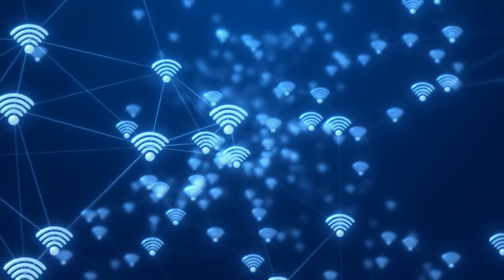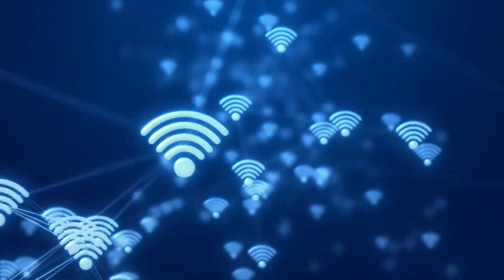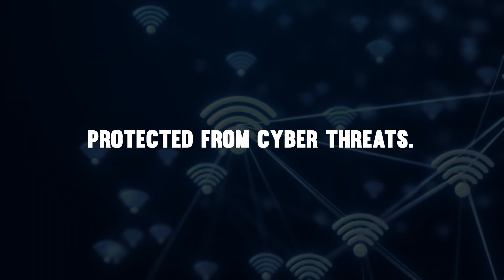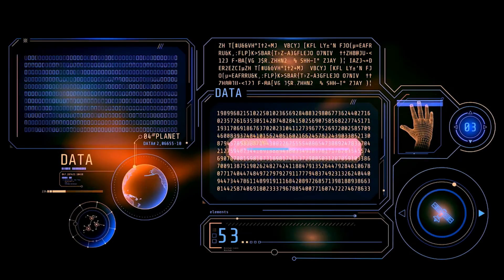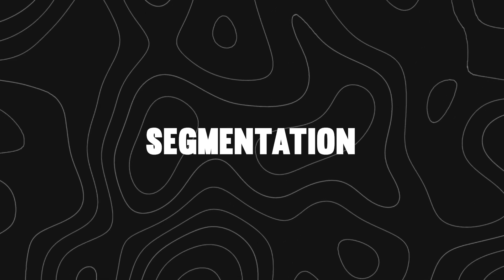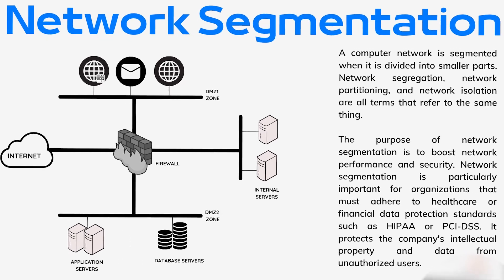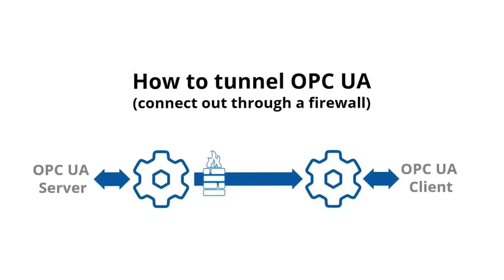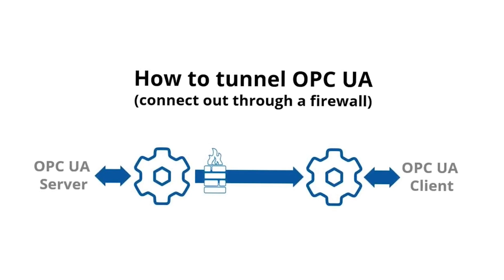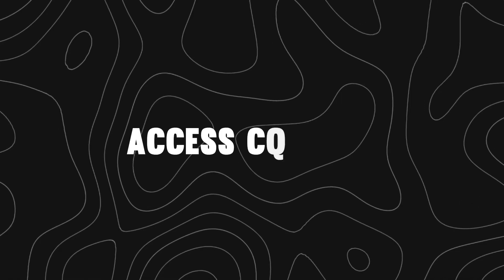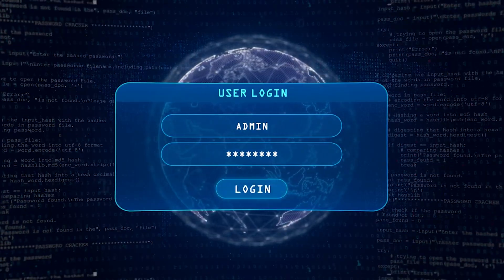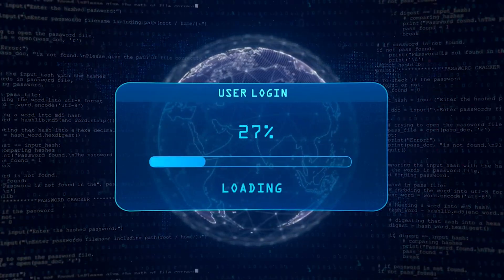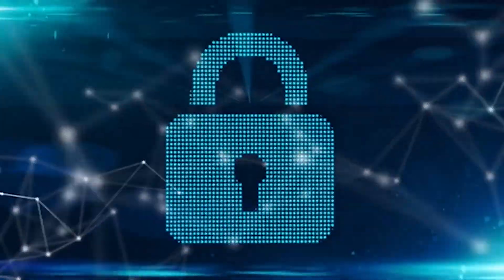With more connectivity comes more risk. IIoT systems must be protected from cyber threats. Encryption. All data between devices and servers should be encrypted to prevent interception. Segmentation. Critical systems should be isolated from external networks. Secure protocols. Use OPC UA with TLS, VPNs, and firewall-protected gateways. Access control. Only authorized users should access devices and dashboards. A single weak point can expose the entire network. Security must be built in from day one.